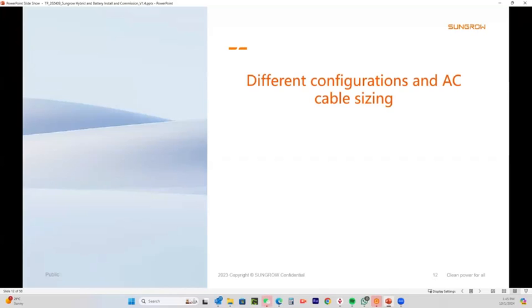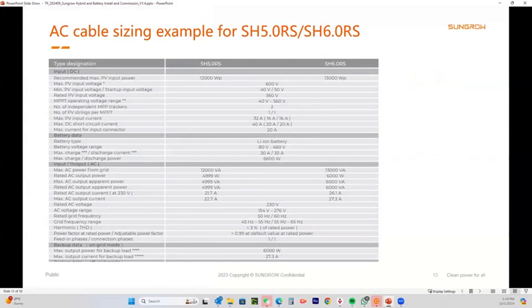Now, we've got different configurations available, and I also want to talk about AC cable sizing here. This is an example, the data sheet for the 5 and the 6 single phase inverter. What I want to bring your attention to is, if you look at the battery data, it says max charge discharge power, which is 6.6 kilowatts. It is possible that can be coming from the grid. For example, at night time, when there's no PV, if somebody has switched on the forced charge because they want to charge the battery up at full power, that will come from the grid, and it's 30 amps.